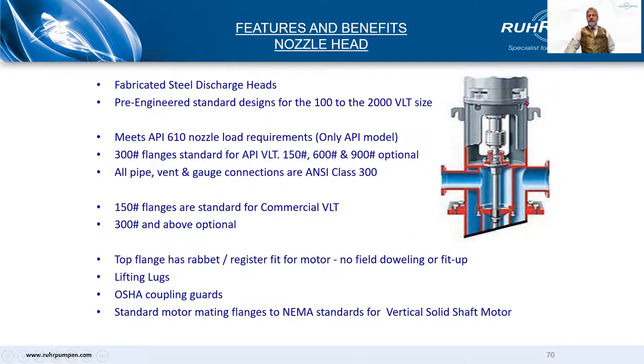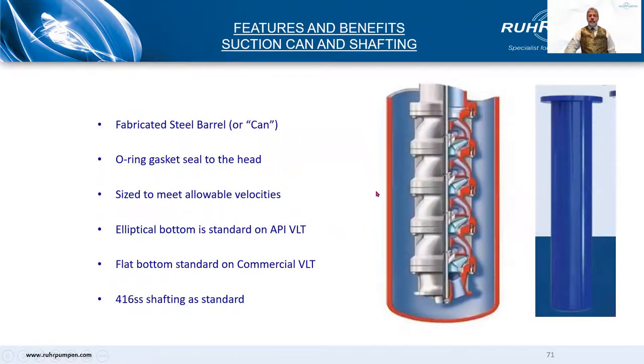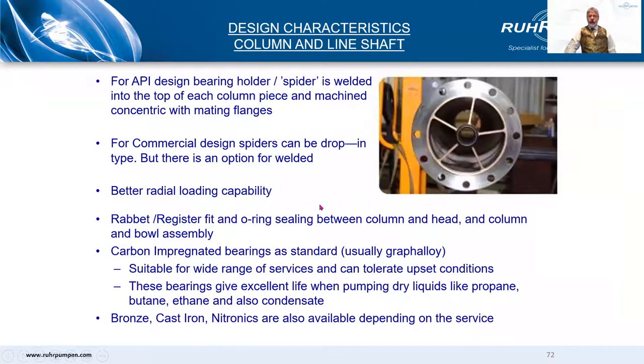Both designs have a register fit, a rabbet fit for the motor sitting on top. The suction can or barrel on the API pump is usually designed for 40 bar. The non-API barrel usually has a flat bottom and is designed just for suction pressure. 416 stainless steel shaft is standard on this type of pump.